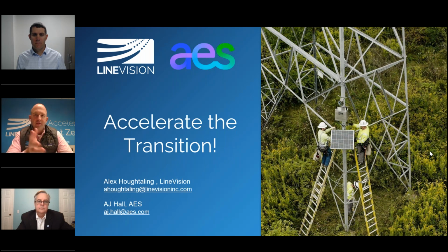And I guess just to be a little bit obnoxious, Larry, but you said traditional versus whatever the opposite of traditional is. We are using the same methodologies that you are for rating your lines. IEEE 738's heat balance equation, that's a traditional way to get capacity.